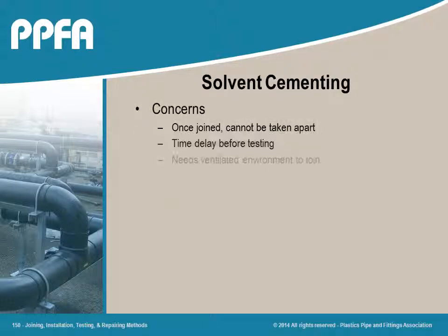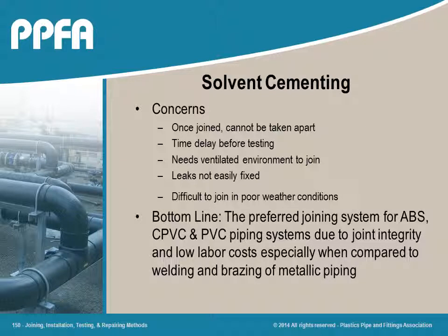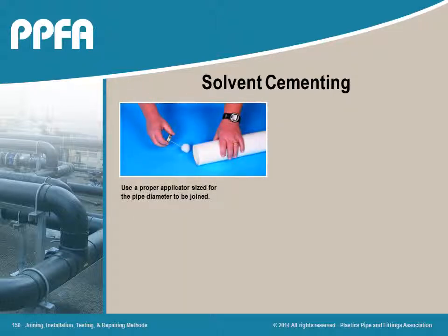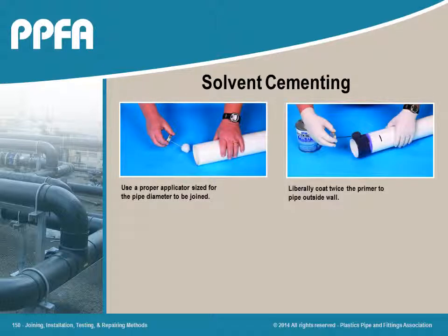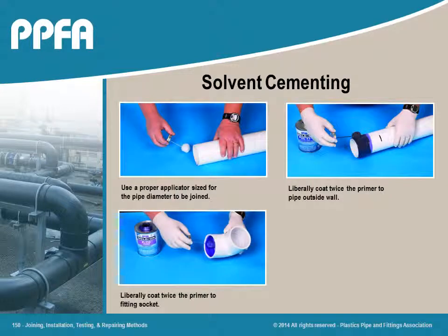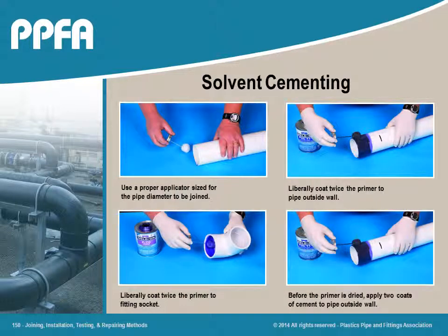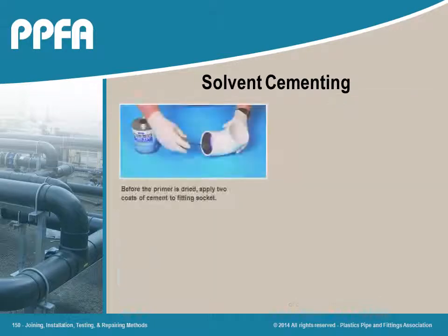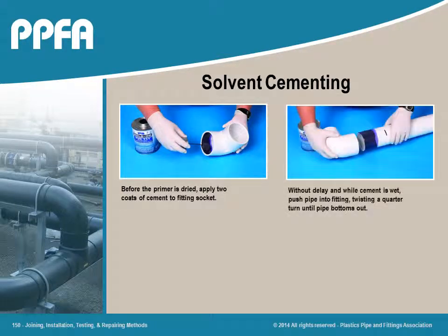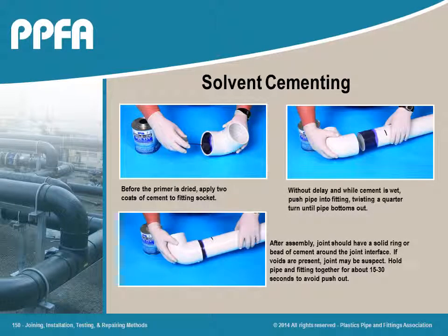The growth of ABS, CPVC, and PVC piping systems is mainly due to the ease of permanently, quickly, safely, and cost-effectively joining these materials. A minimum investment of inexpensive installation tools is required. Solvent cemented joints are chemically bonded and will have cross-sections showing a homogeneous and monolithic bond. If using a brush for cementing, make certain that it is a natural bristle type and with a width of approximately half the pipe diameter to be joined.